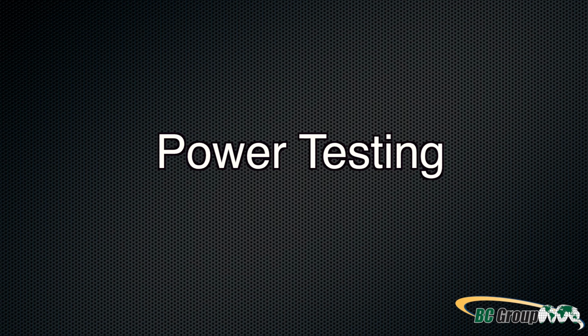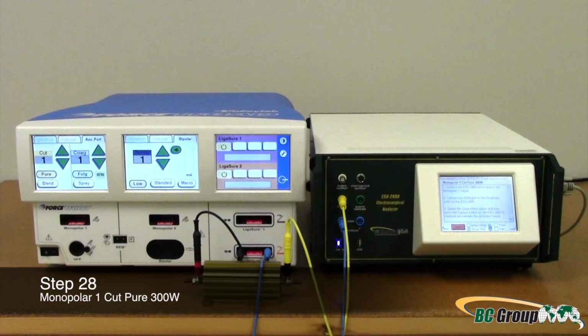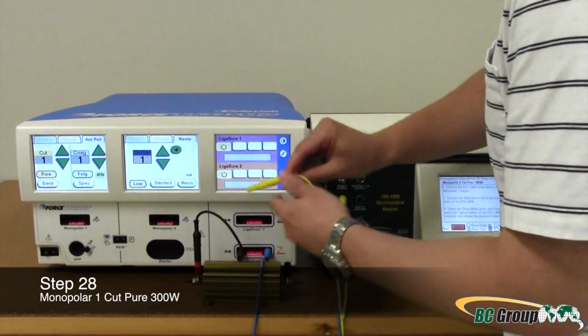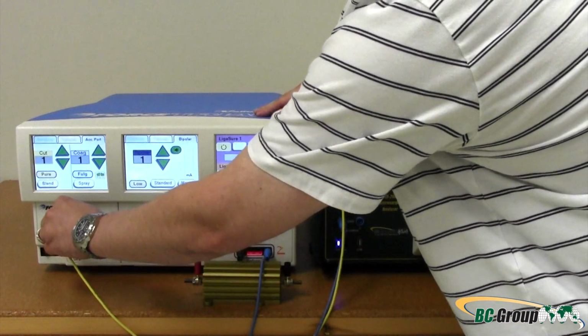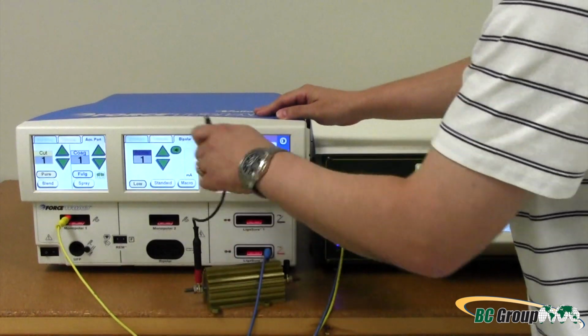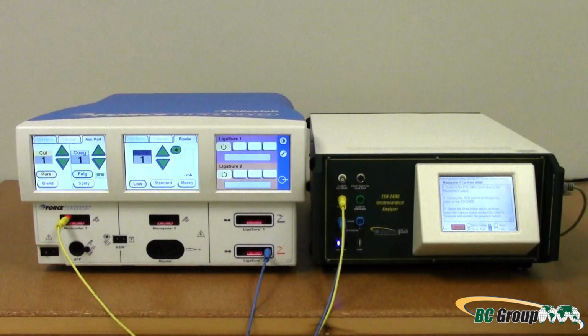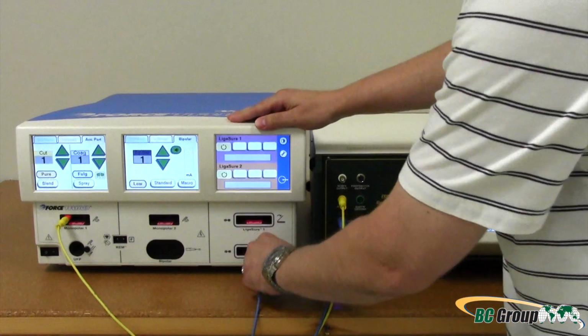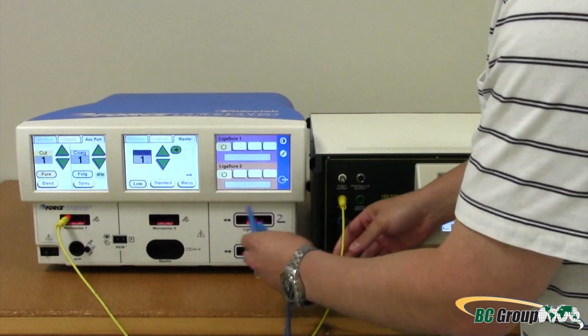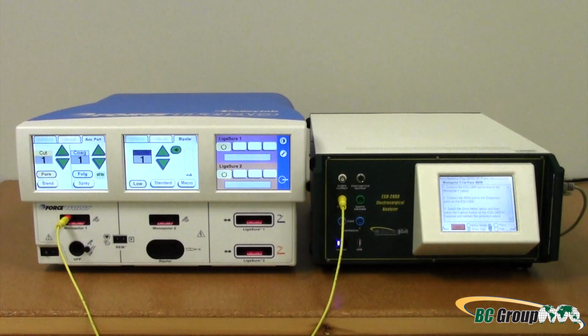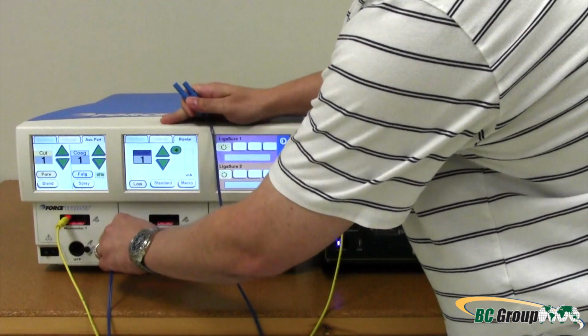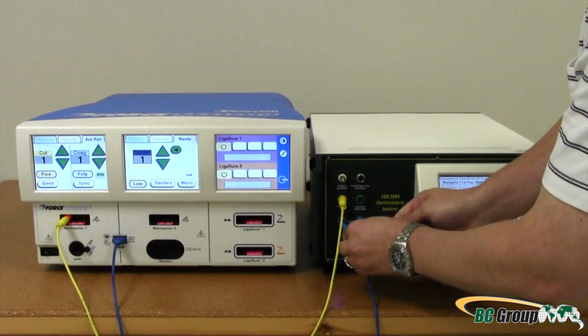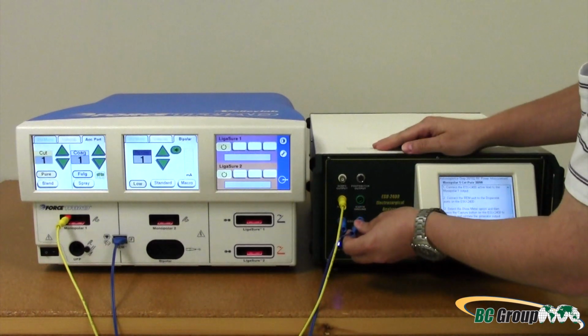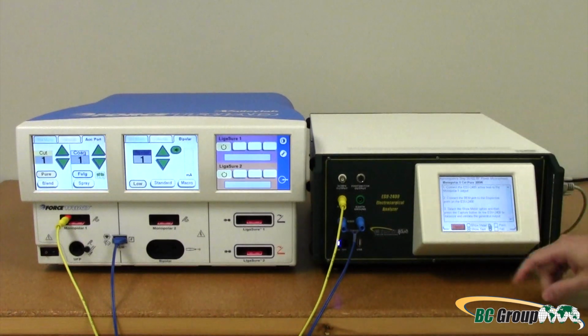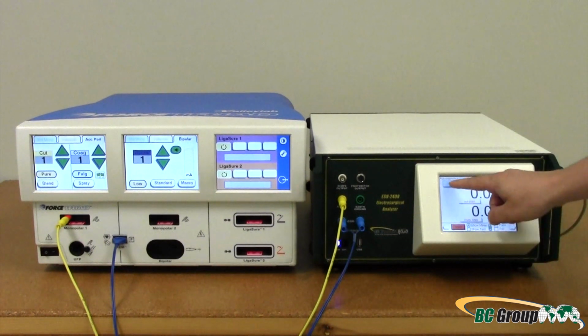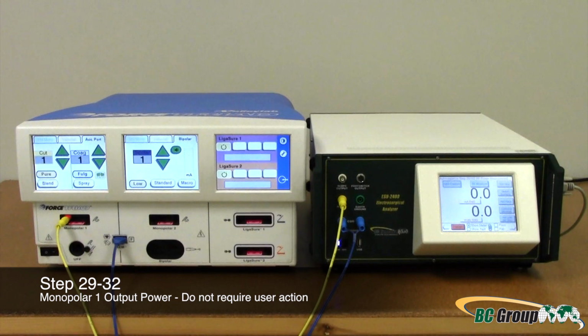Power testing. Step 28. Monopolar 1, cut, pure 300 watt. Connect the monopolar 1 output to the ESU-2400 active port. Remove the resistor, the short jumper lead, and the dispersive lead. Connect the REM port to the dispersive 1 and dispersive 2 ports. Select Show Meter and then press Capture. Steps 29 through 32 do not require user action.